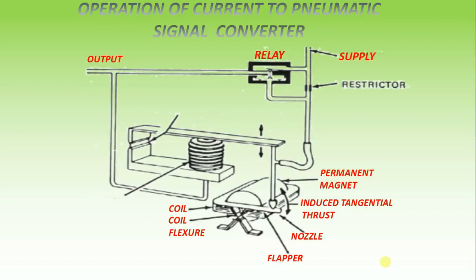This pressure is fed to a feedback bellows which exerts a force on a feedback flexure to move the nozzle and establish a throttling relationship between the flapper and the nozzle, thus producing the output pressure according to the input milliamps.